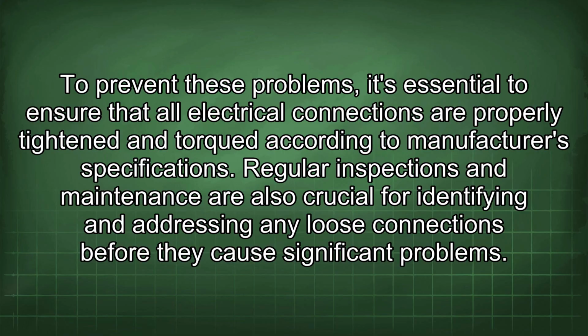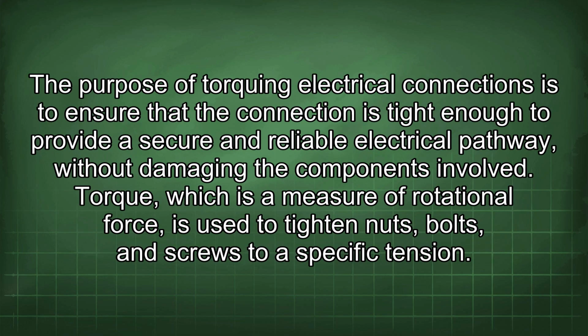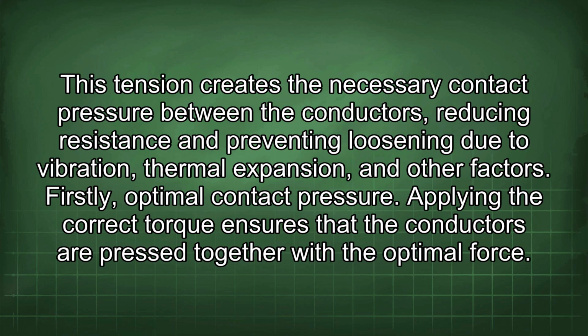Regular inspections and maintenance are also crucial for identifying and addressing any loose connections before they cause significant problems. The purpose of torquing electrical connections is to ensure that the connection is tight enough to provide a secure and reliable electrical pathway without damaging the components involved. Torque, which is a measure of rotational force, is used to tighten nuts, bolts, and screws to a specific tension. This tension creates the necessary contact pressure between the conductors, reducing resistance and preventing loosening due to vibration, thermal expansion, and other factors. Firstly, optimal contact pressure.